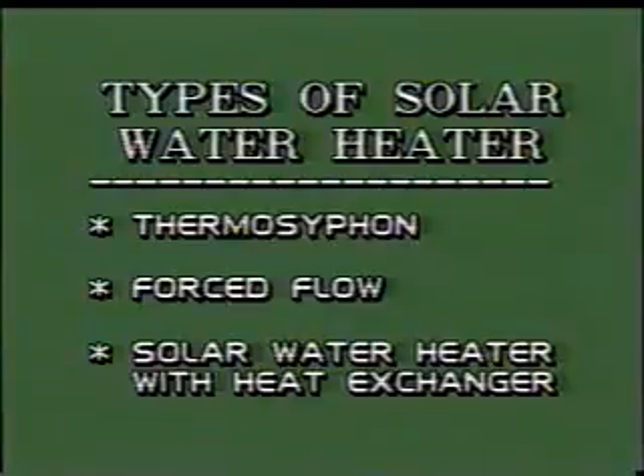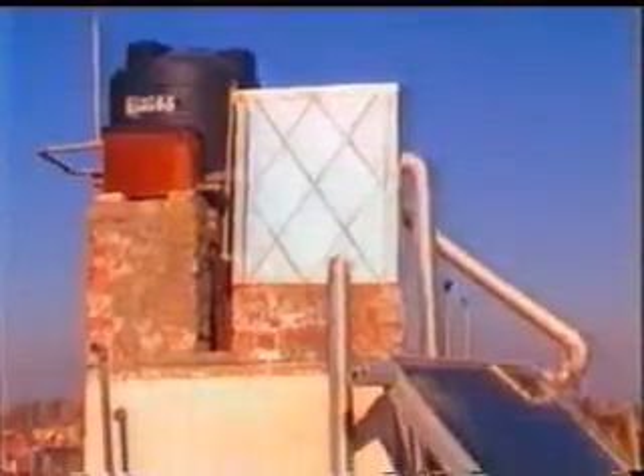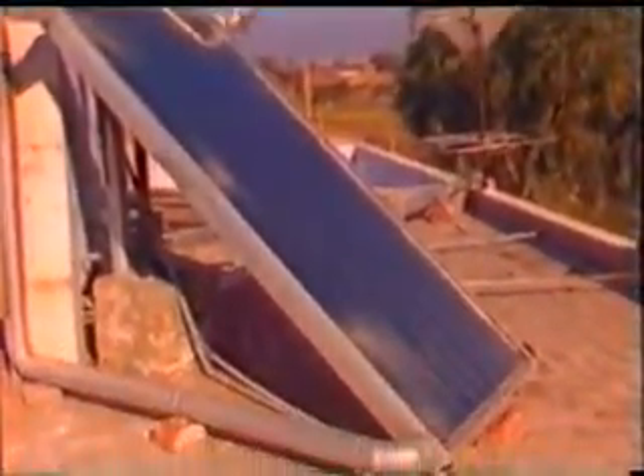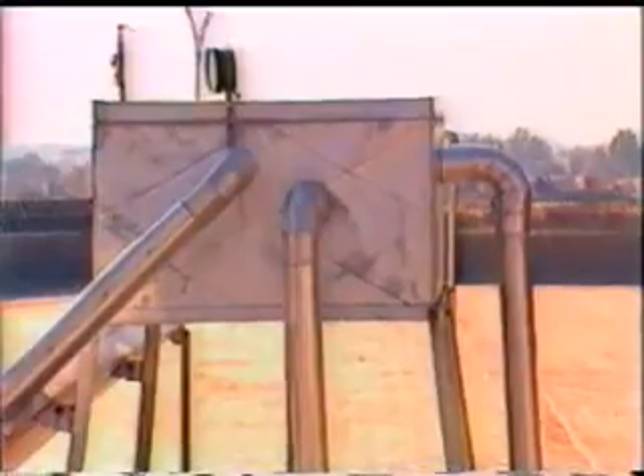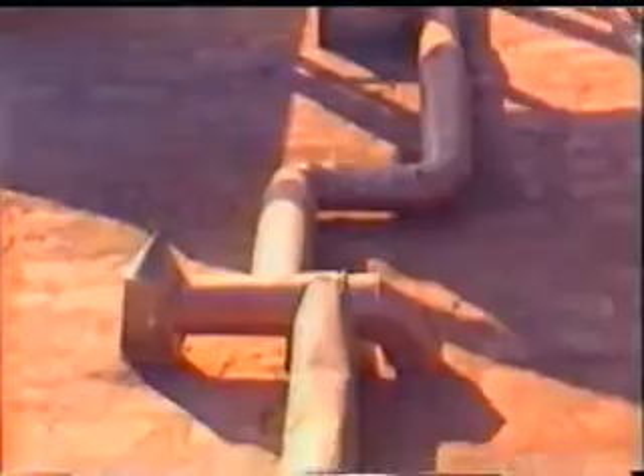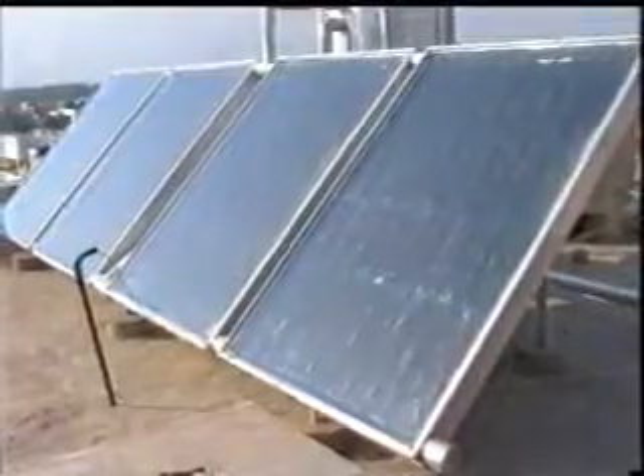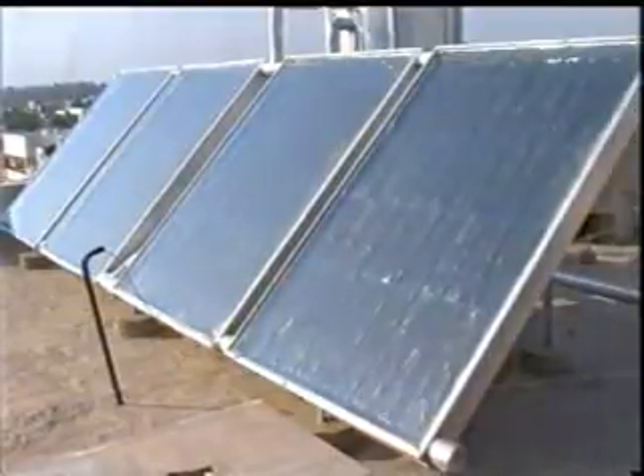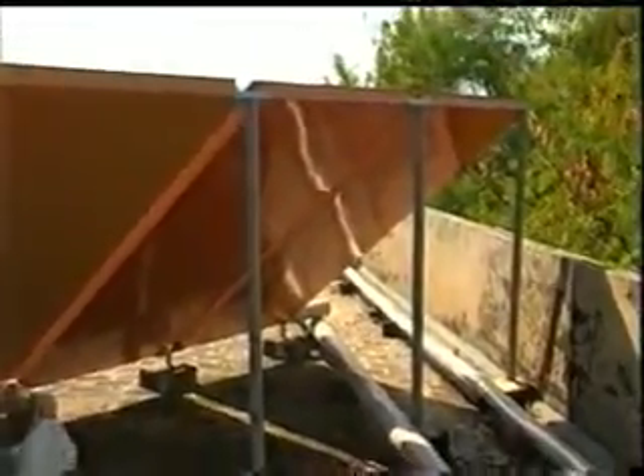Commonly used solar water heating systems are thermosiphon solar water heater, forced flow solar water heater, and solar water heater with heat exchanger. In thermosiphon solar water heater, there is a collector connected to insulated water storage tank and connecting pipes. Part of the solar water heating system is the collector. The collector comprises of front glazing of toughened glass, blackened metallic absorber with thin riser tubes, insulated with glass wool, and held in the collector box.